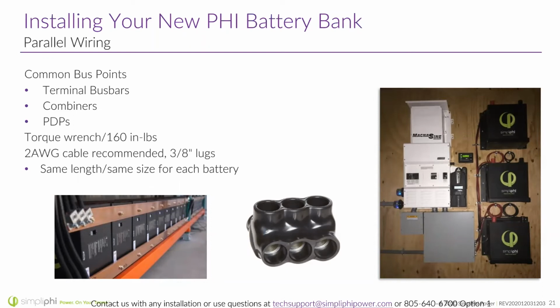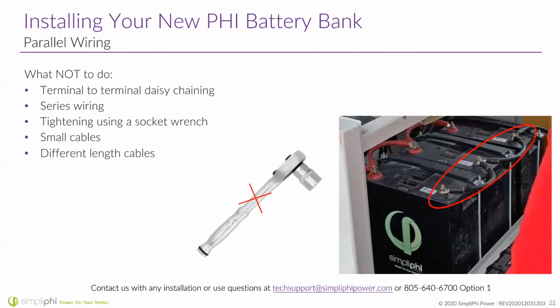Be sure to use a torque wrench and calibrate that wrench to 160 inch-pounds. So one thing to avoid here is using a socket wrench. You can actually over-tighten the terminals using that socket wrench and potentially strip the threads or even snap the metal terminal. The torque wrench really applies to all batteries, though. I wouldn't say it's specific to us. It's just a good thing to keep in mind.